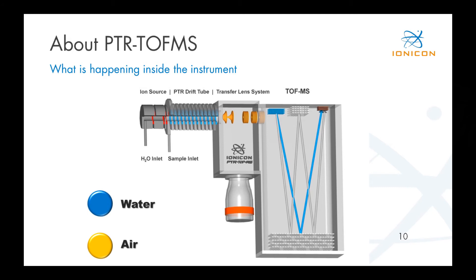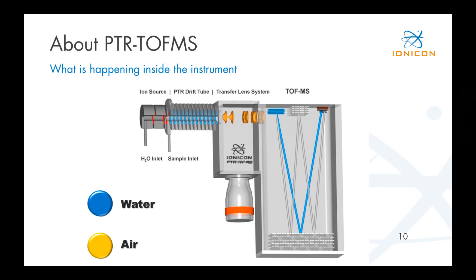After the ion source, the H3O+ is injected into the so-called drift tube — some people also call this the reaction region — and you also have a sample inlet into this drift tube. This sample inlet is constantly drawing in outside air containing your molecules of interest. In the drift tube, the H3O+ reacts with all compounds that have a higher proton affinity than water and transfers its proton to the compound of interest. At the end of the drift tube, you end up with the ionized compound of interest, which is then transferred into the transfer lens system. This system differs depending on the model: conventional transfer lens system, ion guide, or ion funnel.